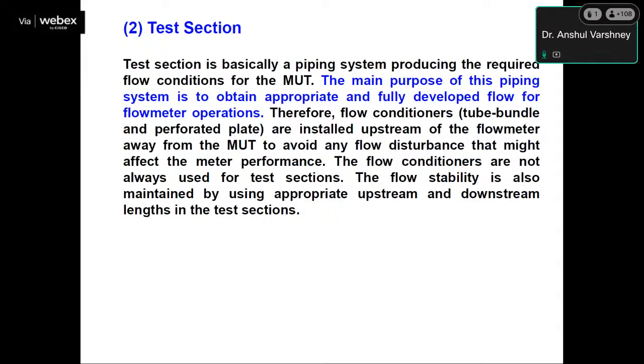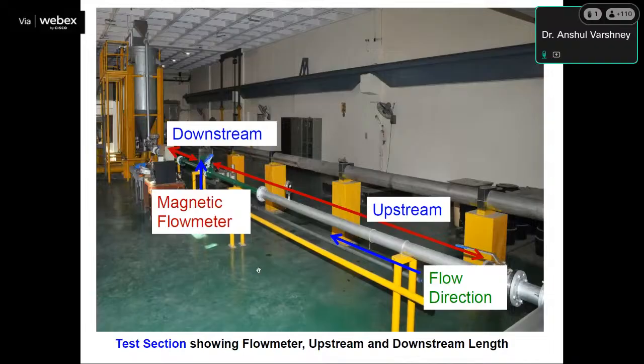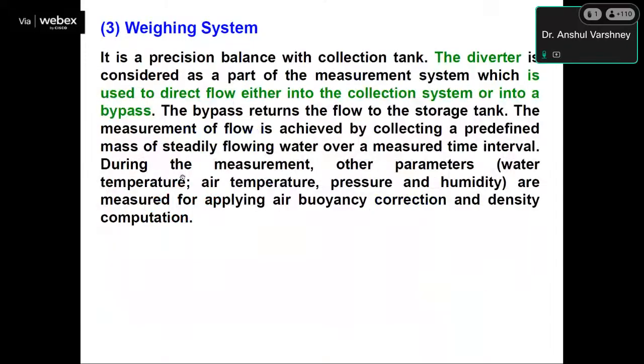Next is the test section. The test section is a piping system producing the required flow condition for the meter under test. The main purpose of this system is to obtain appropriate and fully developed flow for flow meter operations. Therefore, flow conditioners are installed upstream of the flow meter and away from the meter under test to avoid any flow disturbance that might affect the meter performance. This is the test section, which shows the flow meter upstream and downstream lengths. This is the flow meter which has been mounted for test. This is the upstream length and this is the downstream length.